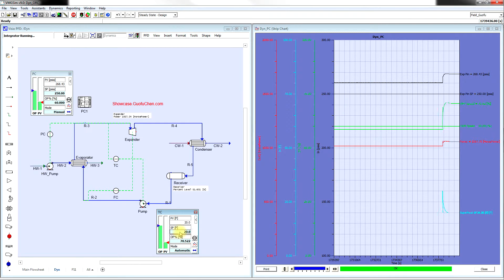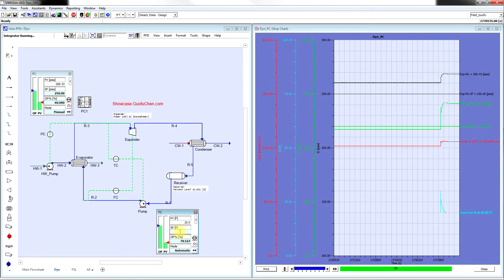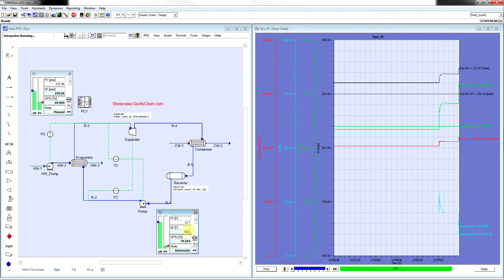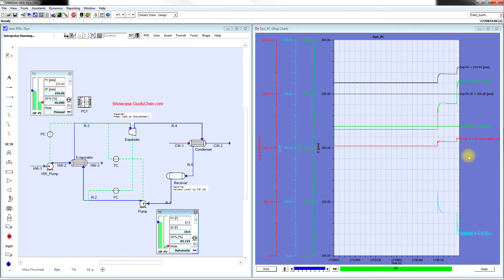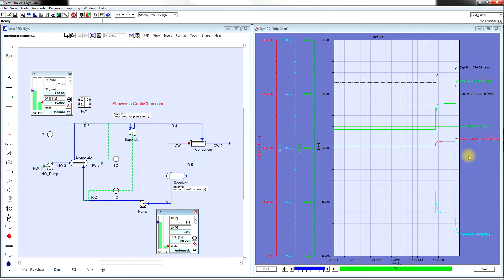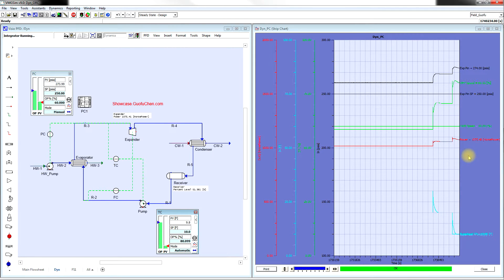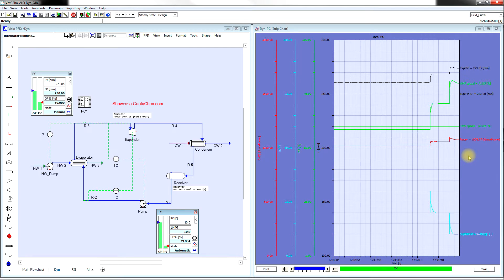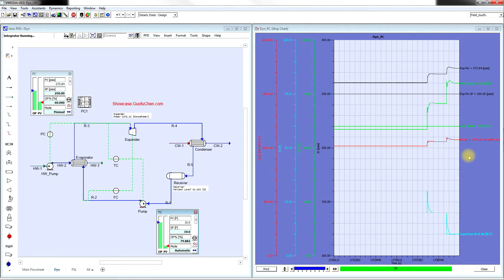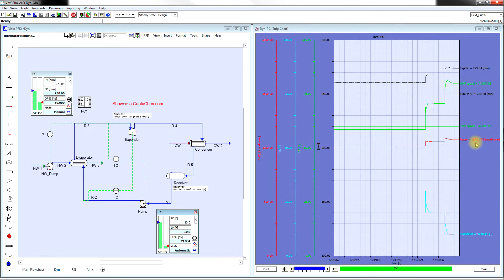So what's going to happen if we reduce the superheat into 10 Fahrenheit again? Looks like we are producing even more. We are producing about 1075 horsepower.